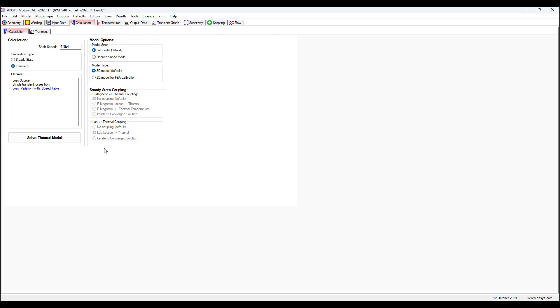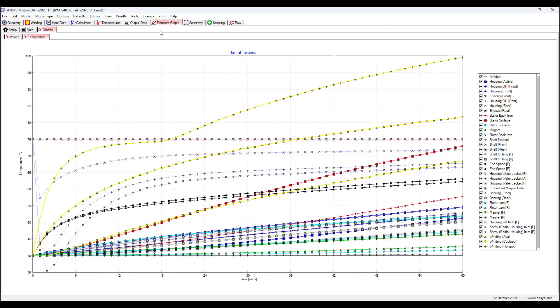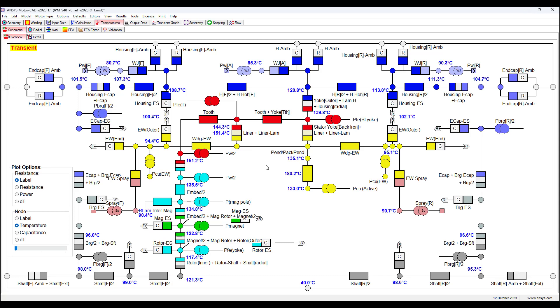Running the thermal simulation will take a few minutes, but once we get the results we can see the temperature distribution in the thermal circuit. Here's a trending graph of the temperature plots for all objects in the motor. The temperature overview shows the thermal circuit using thermal circuit components for conductive thermal resistance, radiative and conductive thermal resistance, power losses, heat sources, etc. This thermal circuit is the complete heat transfer model of the motor and will help you make design decisions.